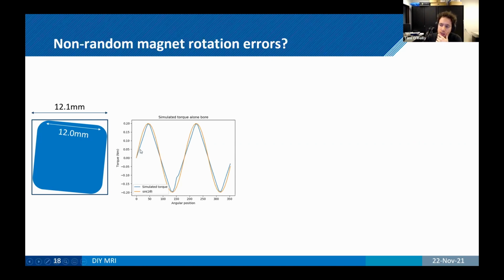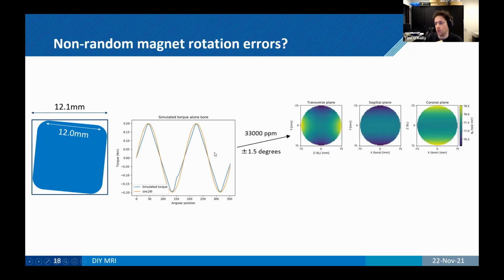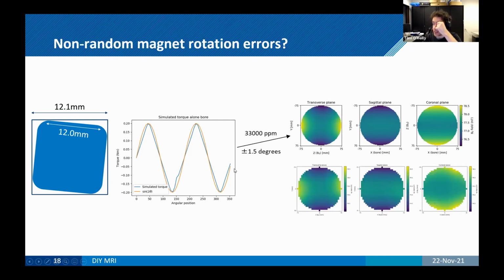But obviously the magnets themselves, when they're in place, will feel some torque because of the nearby magnets and the main magnetic field. And that torque has this cosine, or sine 2 phi pattern on it, where phi is the azimuthal angle as you're going around the circle, so the polar angle. If there's a positive torque on it, it can rotate to the right. If there's a negative torque on it, it's going to rotate to the left, then right, then left. What you end up with as a field pattern is this. So this is 33,000 ppm if the magnets can rotate 1.5 degrees, which is not a lot. And if we put that against the magnet for which we simulated this, it's a very good agreement. That really shows how important it is to build your system well, because a 1.5 degree rotation is really not a lot.